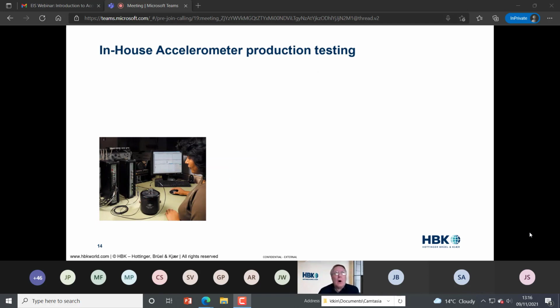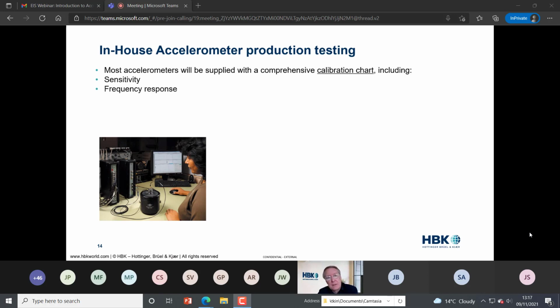Okay, now if you buy an accelerometer from most of the manufacturers, you will also get a calibration chart. And this is not something that you should just put in the drawer and forget about until it's time for recalibration. There's a lot of useful information on the calibration chart which can help you in deciding whether a particular accelerometer is suited to the application before you begin, such as sensitivity, frequency response, the mounted resonant frequency, the effects from environmental influences, etc., etc.